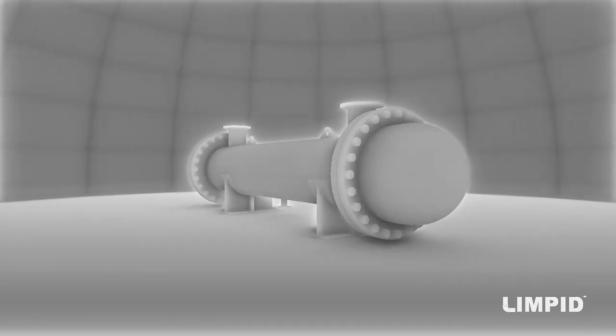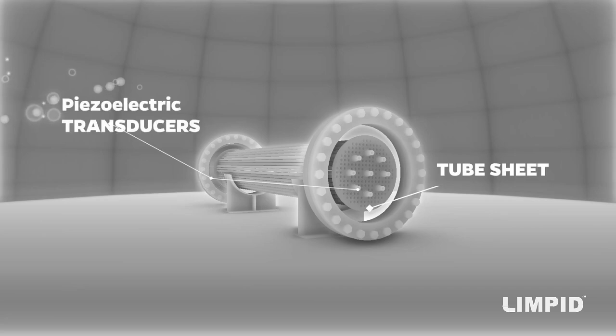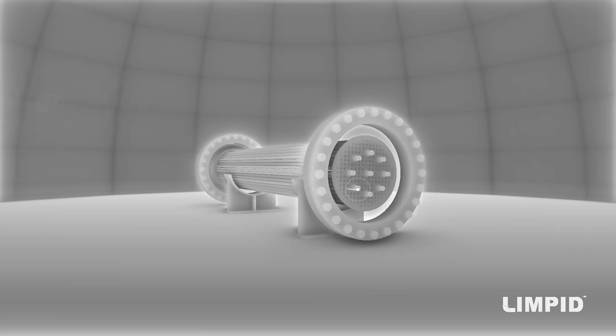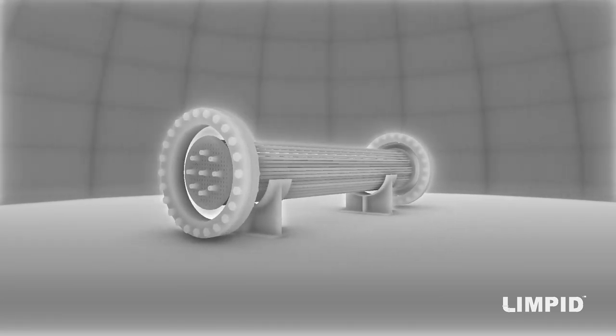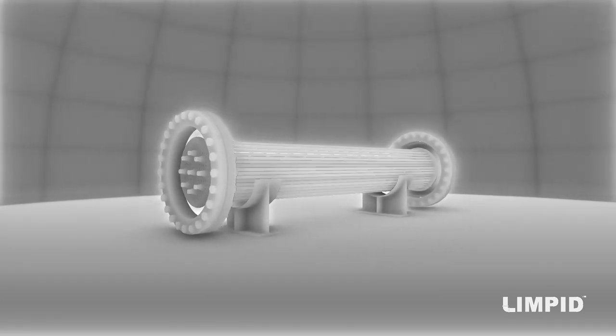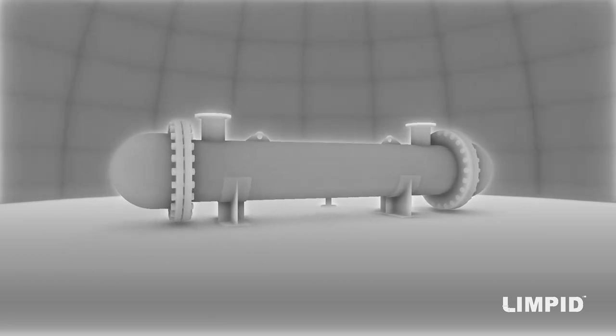The LIMPID system involves installation of piezoelectric transducers at suitable positions on the tube sheet of the heat exchanger. A resonator, or generator, drives the piezoelectric transducers that convert electric energy into ultrasonic vibrations. The current passes to the piezoelectric transducer in a pulsating way. These arrangements make the tubes or plates vibrate at ultrasonic frequency at low amplitude, which prevents crystal deposition on the heating surface.